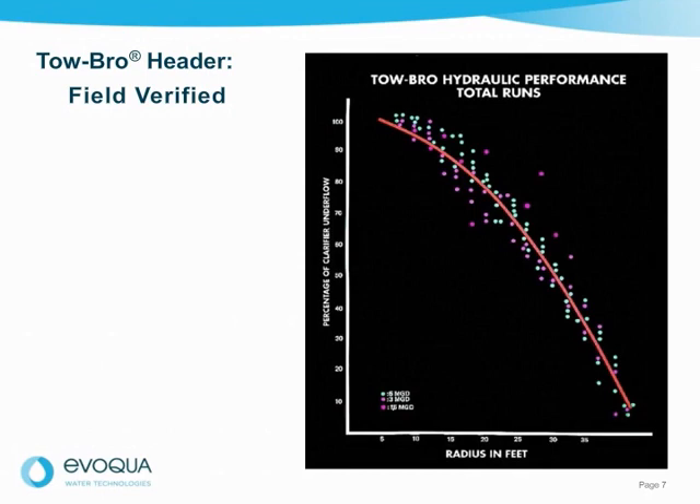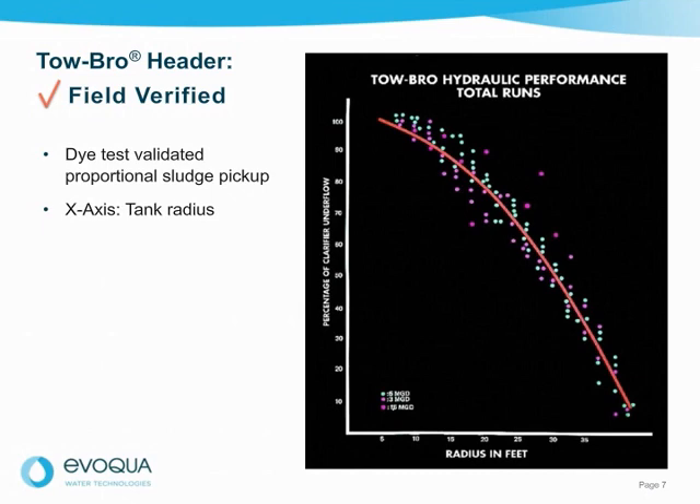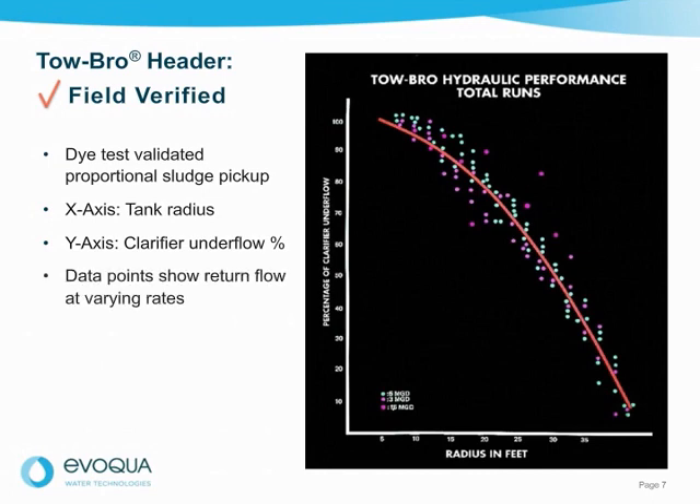The Tobro unitube header is also field performance verified for uniform sludge removal based on flow area swept. A dye test was performed to measure the percent of sludge pickup along a tank radius. The x-axis shows the tank radius, and the y-axis shows the cumulative percent clarifier underflow, or return sludge. The colored data points show the varying flow rates used for individual test runs. The solid line represents ideal sludge pickup in proportion to the floor area swept. By closely following the ideal curve, the field test validates the model used to design headers for uniform sludge pickup across the full radius of the tank.